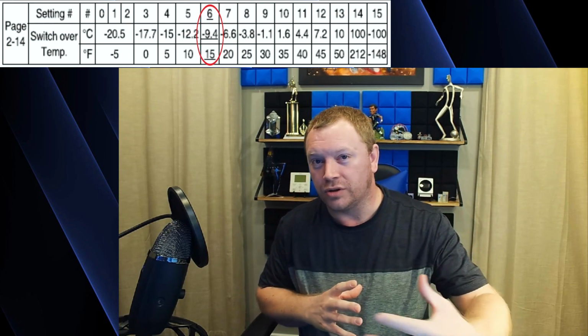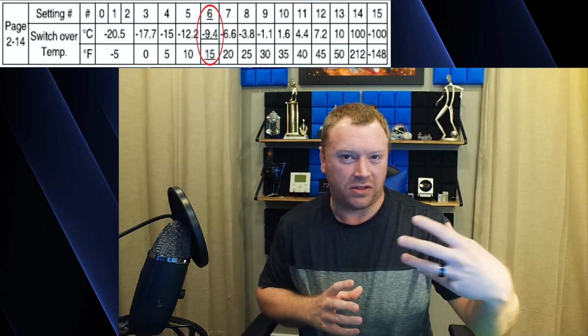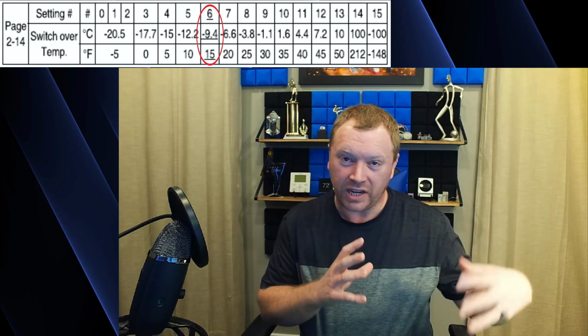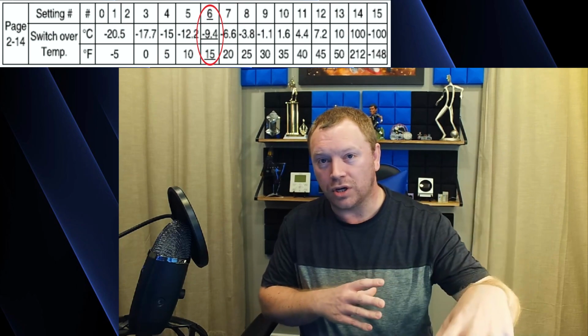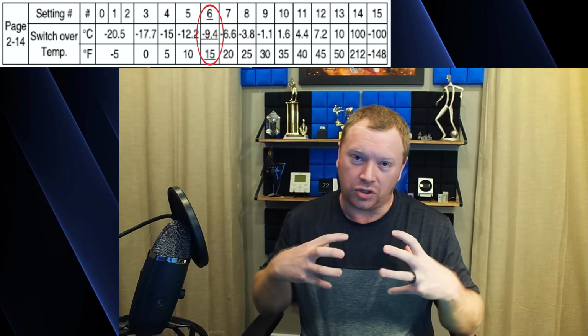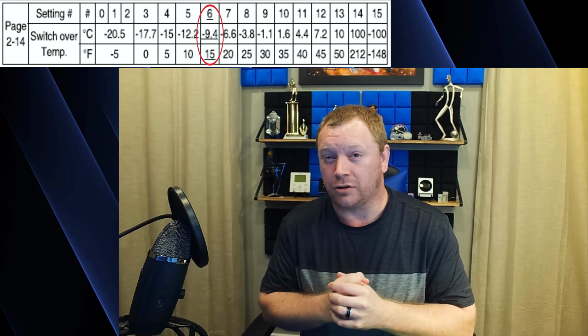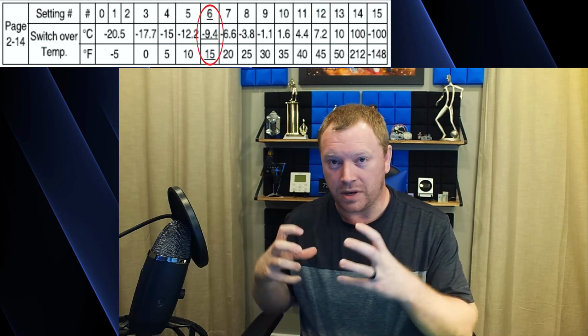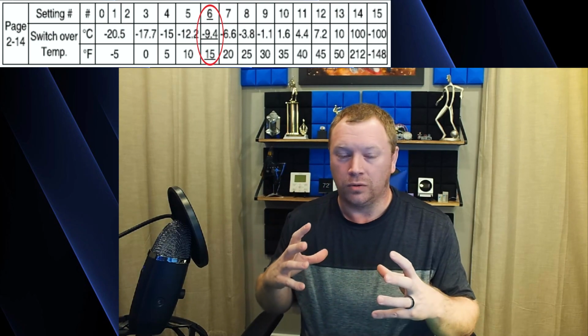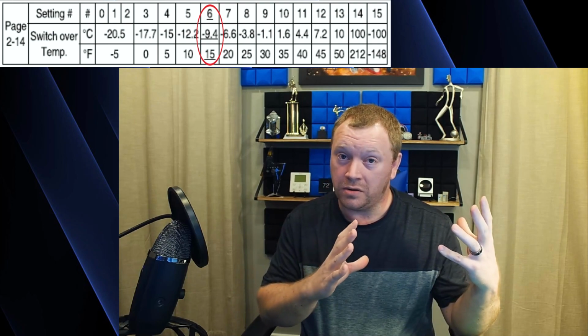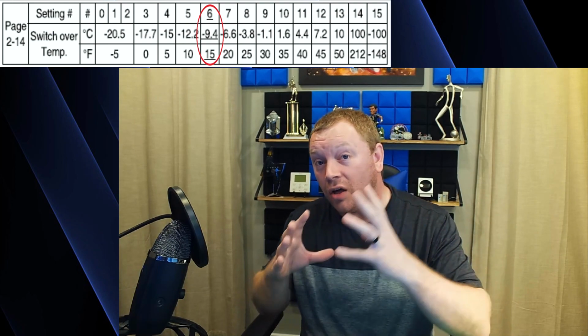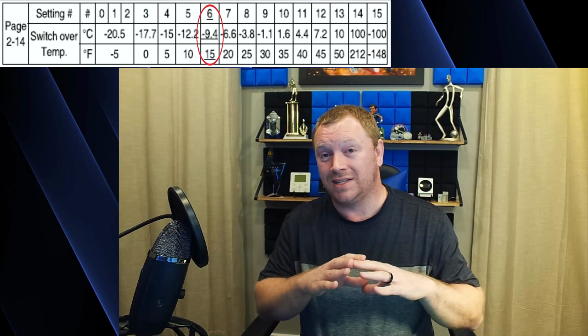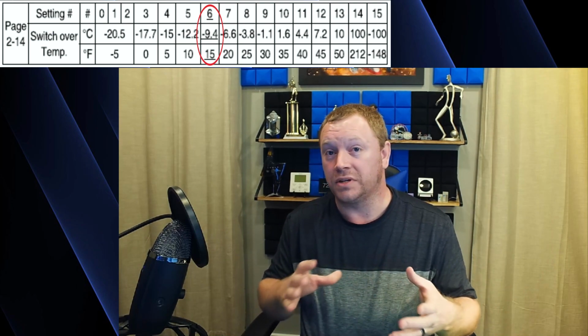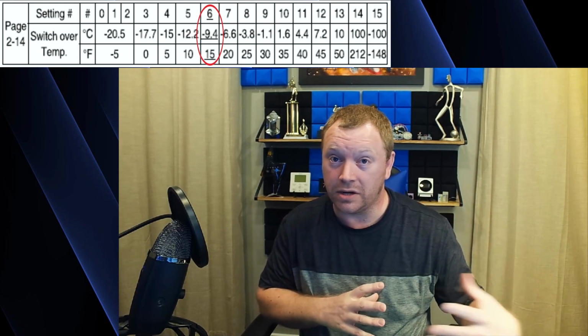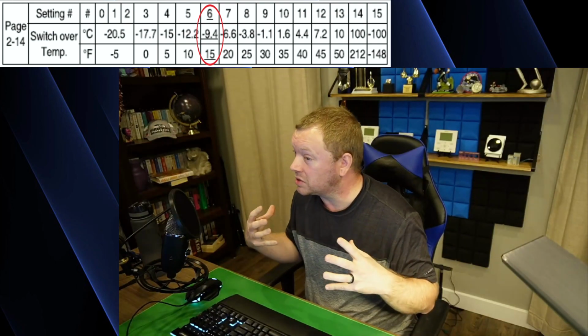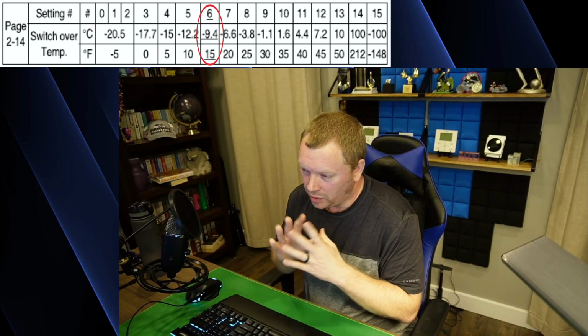If you have other indoor units like wall mounts, cassettes, or other ducted units, then the heat pump will technically continue operating for those zones. And then the gas furnace will just close down the EEV, the electronic expansion valve, for the CXTQ A-coil, or run the gas for that zone. One of the cool things about VRV Life is you can run the gas heat and other heat pump zones simultaneously. So that's one of the reasons I put it on my house. I can run the gas downstairs and I can run my wall mount in the garage all simultaneously. It's pretty cool. But I digress.